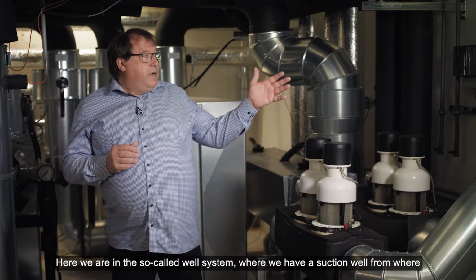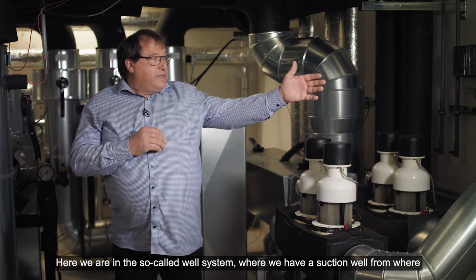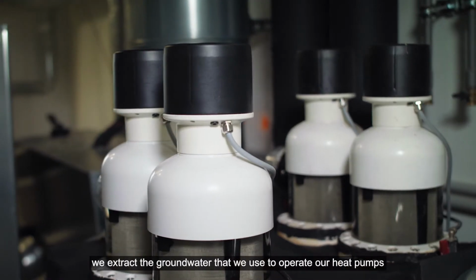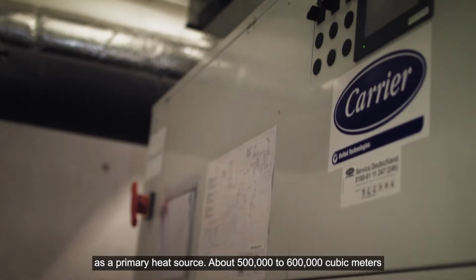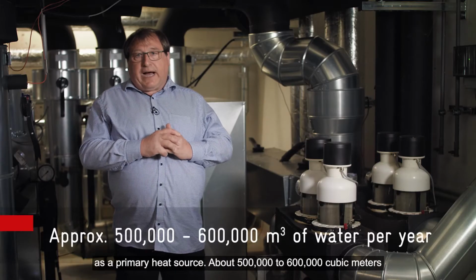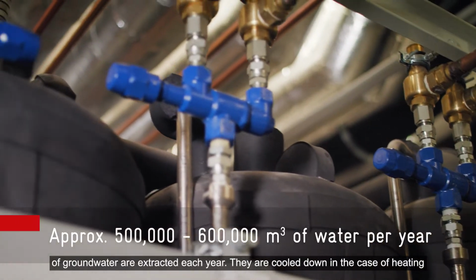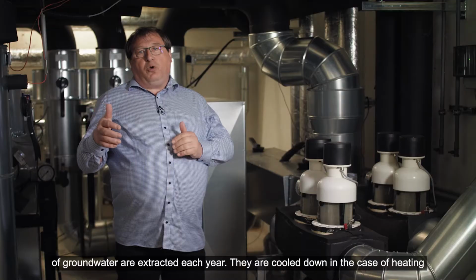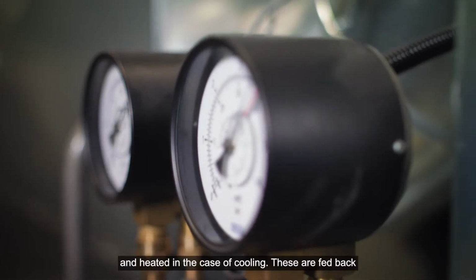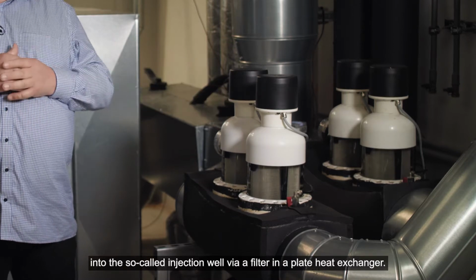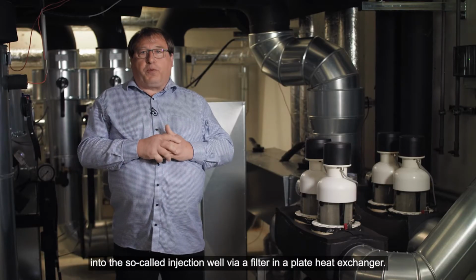Here we are in the so-called well system, where we have a suction well from where we extract the groundwater that we use to operate our heat pumps as a primary heat source. About 500,000 to 600,000 cubic meters of groundwater are extracted each year. They are cooled down in the case of heating and heated in the case of cooling. These are fed back into the so-called injection well via a filter in a plate heat exchanger.